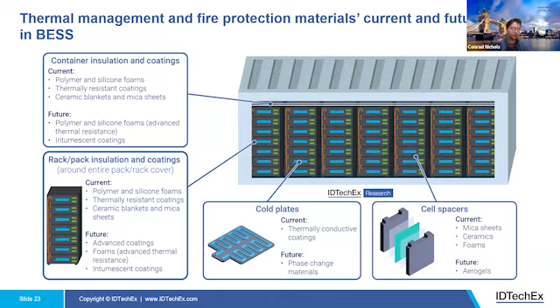So we've touched on some of the passive materials and what we would expect from that side of things. If we now look at the active technologies, these thermal management systems and technologies typically refer to cooling technologies, sensors, fire suppressants, and venting. And active cooling technologies can ensure that batteries operate at optimum temperatures. These help to prevent hotspots and temperature gradients being formed across a cell and a pack, which can ultimately lead to a thermal runaway event or show the early signs of it. And indirect liquid cooling, which relies on the cold plate technology that I mentioned, is the dominant choice for grid scale and C&I BESS deployments in the current market. And this is due to its superior heat efficiency over air cooling.